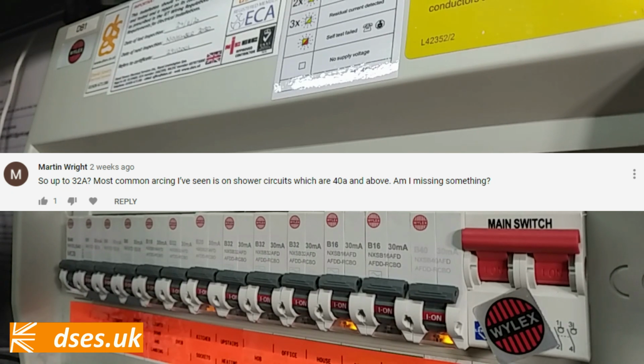A lot of people already have secondary enclosures as they had a shower, extension, new kitchen, EV charger or solar PV added on in recent years. So you may end up changing out that secondary enclosure or even adding a third. Crikey. Martin Wright says, so up to 32 amps? Most common arcing I've seen is on shower circuits which are 40 amps and above.